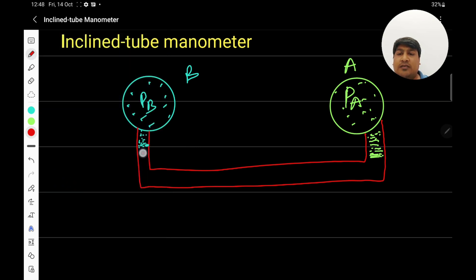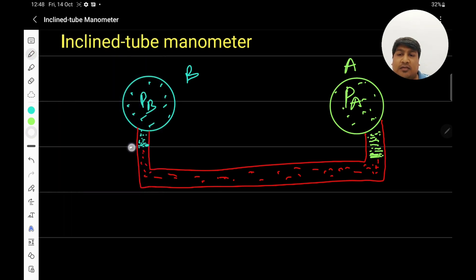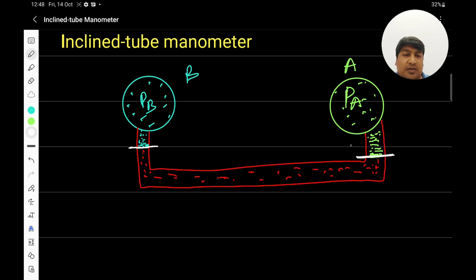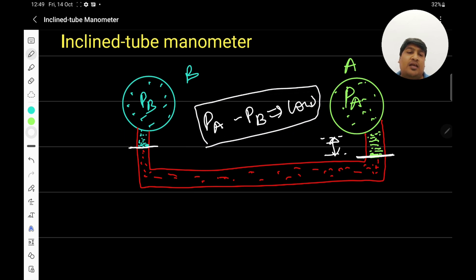A third fluid is inserted into the tube for the measurement of pressure. To measure the pressure difference between the two points, we have to figure out the difference in levels: the liquid in the left tube is at one level and the liquid in the right tube is at another. Sometimes the difference between these two levels is very low, making it very hard to differentiate. This kind of situation arises whenever the pressure difference between the two chambers is very low. In such scenarios we need to use an inclined tube manometer.